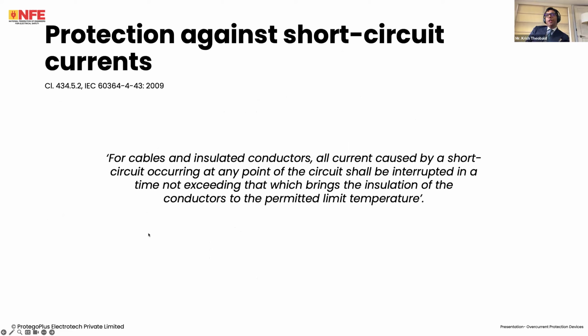Now, how do we protect our cable against short circuit currents? We've sized our cables for current carrying capacity. We've sized our cables for voltage drop. We also sized our cable to ensure that the earth fault loop impedance is such that the device disconnects for protection against electric shock. But can the cable now withstand the current for the required time? Well, for cables and insulated conductors, the standard says that all current caused by a short circuit occurring at any point of the circuit shall be interrupted in a time not exceeding that which brings the insulation of the conductors to the permitted limit temperature. If you remember earlier, we spoke about normal operating temperature and limiting temperature. Limiting temperature is the temperature that the cable achieves during a fault for however many milliseconds or seconds.